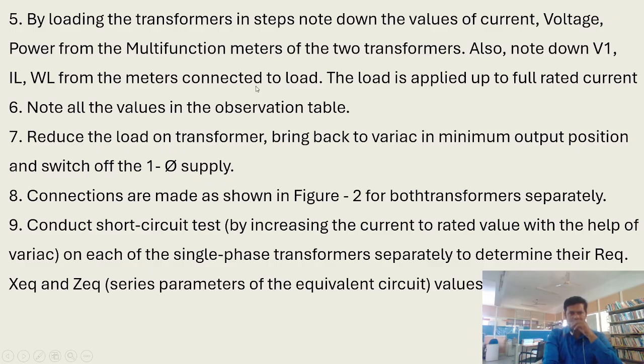Then also note the V1, IL, WL from the meters connected to the loads. Load is applied until we get the rated current. Then note all the values in the observation, make the tabular columns and note the values. Then reduce the load step by step and bring the variac back to the minimum position.